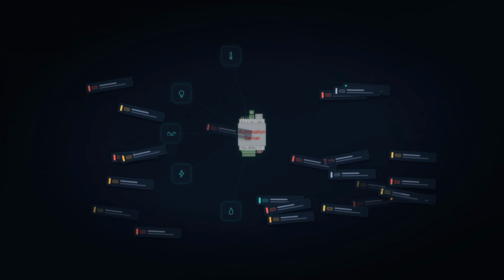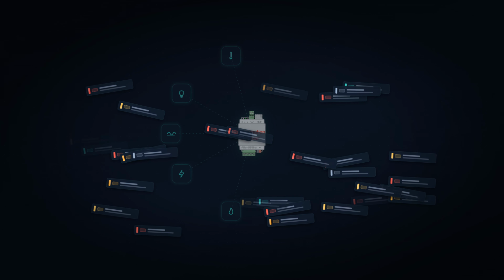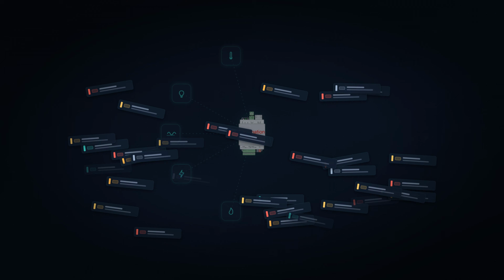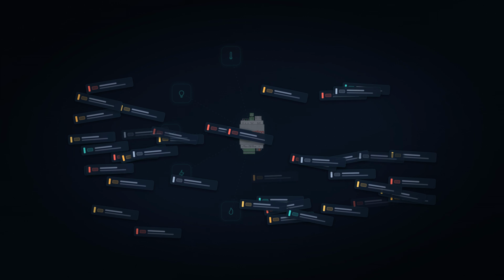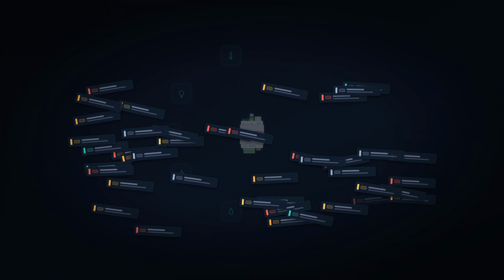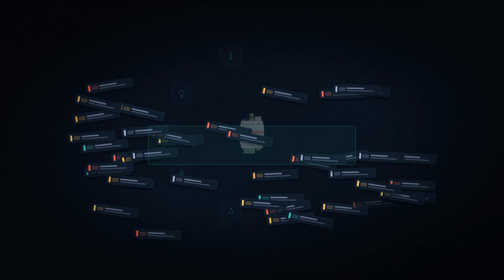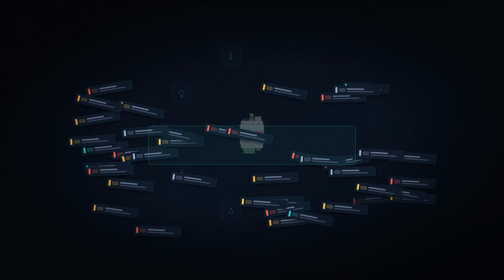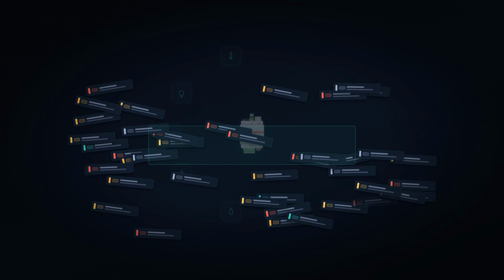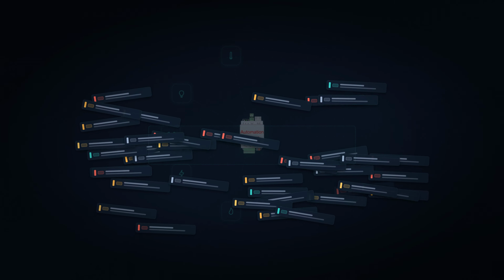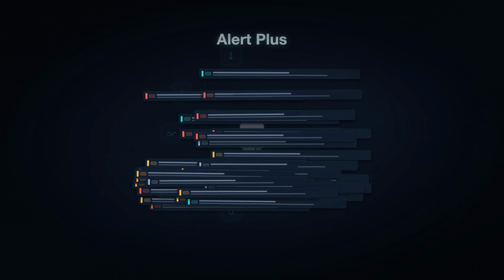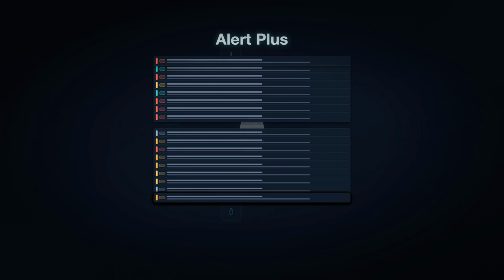Alarms arriving back-to-back leave the operator unable to act, and it becomes unclear which alarm was acknowledged, when, and by whom. The alarm discipline that major BMS platforms have matured over the years, following each alarm's state from start to finish, ranking it by importance, suppressing needless alarm floods, and recording every action taken, has until now been the missing layer on the automation server. Alert Plus fills exactly this gap.